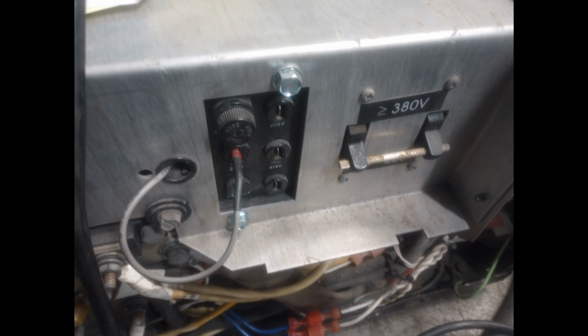Millers usually just operate poorly if the input voltage is wrong, while Lincolns often have a fuse in line with the control transformer. Most larger Lincolns have some kind of panel on the back of the machine that hides voltage tabs. If you're going to operate a Lincoln that you haven't operated before, I would suggest inspecting the panels on the back before applying power to it.